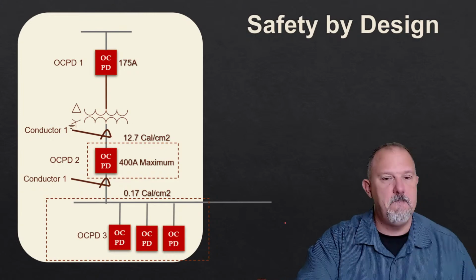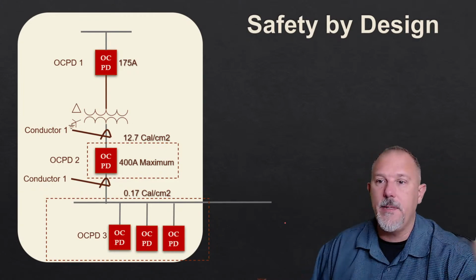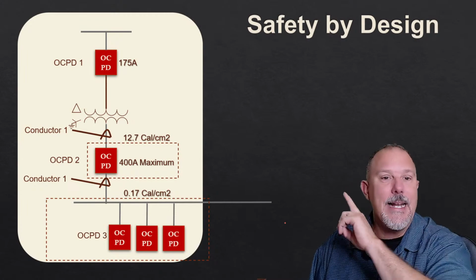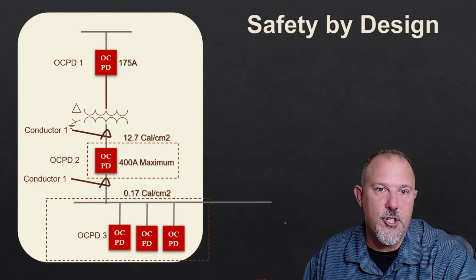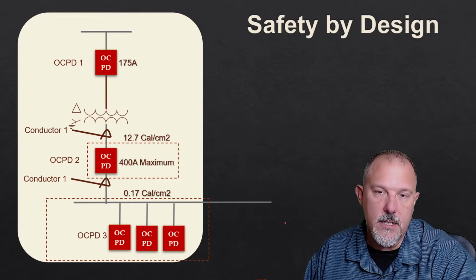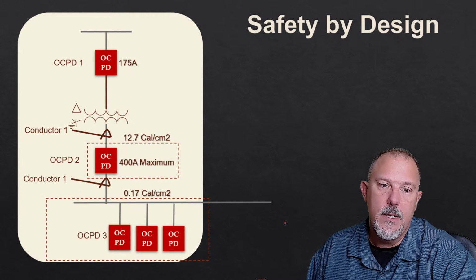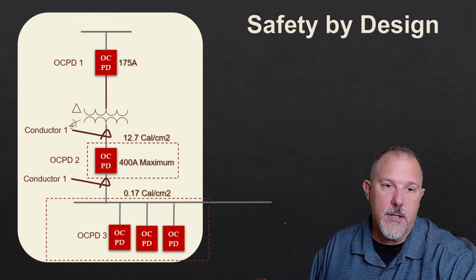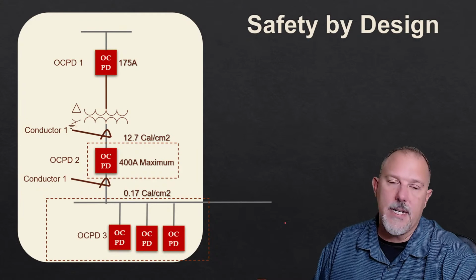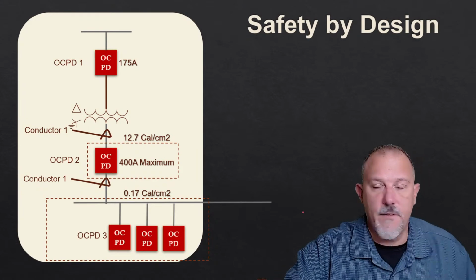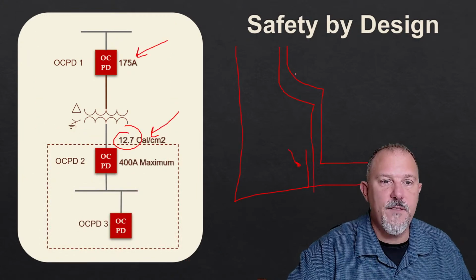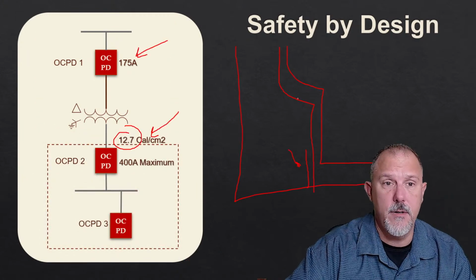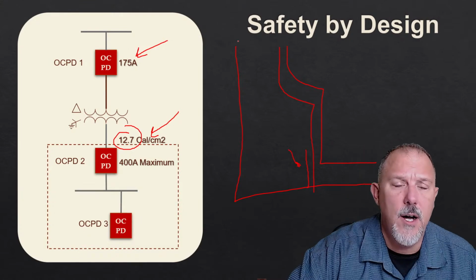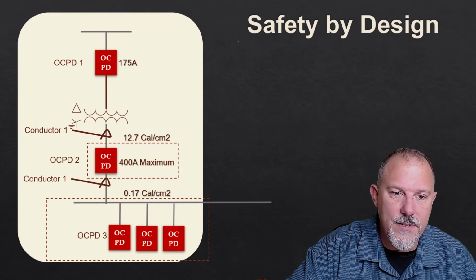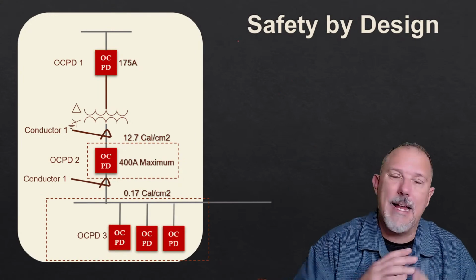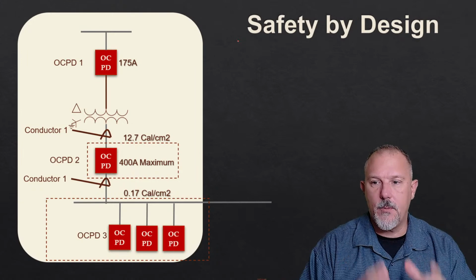And in my opinion, it doesn't need to just be at the service equipment. It can also be at the secondary of any transformer in your power distribution system. It doesn't just have to be a 1600 amp breaker. Because look, I'm showing you right here a 400 amp secondary, right? So this is a 400 amp panel. I went from 12.7 calories, because I'm relying on a 175 amp breaker on the primary of that transformer, down to 0.17, because all I did was break out the main. Separate that.